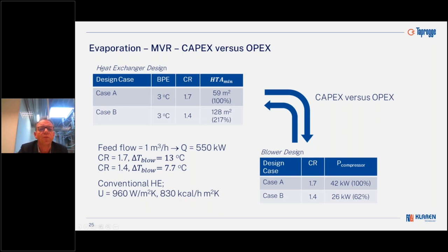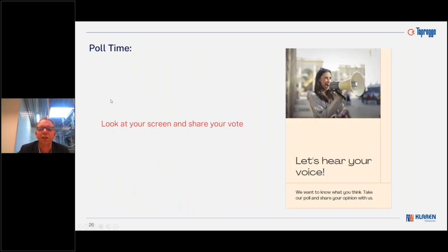But when I reduce my compression ratio, I also get a lower temperature, and you see my heat exchange surface goes to 217% of the original heat exchange surface in case A. So that's a substantial increase, meaning more investment. But on the other hand, if we look at the energy consumption, with the lower compression ratio, meaning more area, you see how much lower the electrical energy is that the compressor will use. This is only 62% of the original 42 kilowatt. So with MVR, it's very important that you make a selection between going for some more investment but lower energy use, or vice versa. This is a very important thing to keep in mind with MVR systems. I think we can go to the next slide, but I think this is time for a poll.